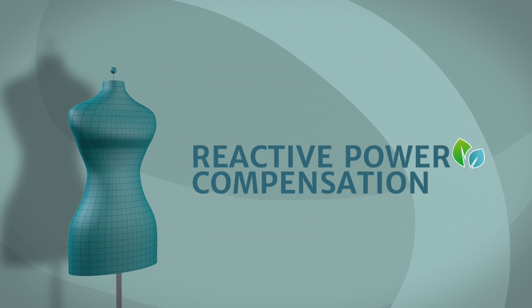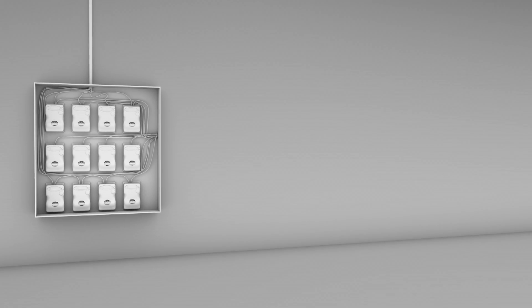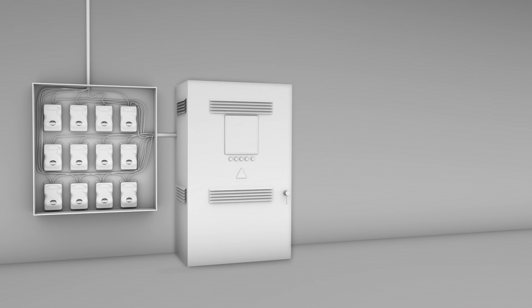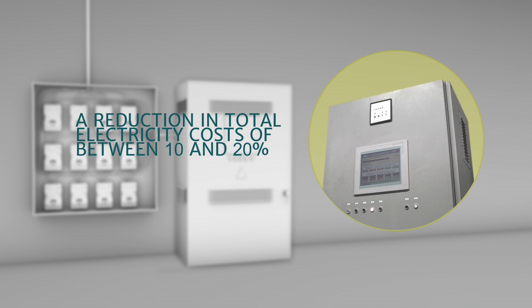The reactive power used by electric motors is stored for a few fractions of a second before being released into the grid. The installation of a simple phase advancer helps reduce total electricity costs by between 10 and 20%. As soon as possible, we installed power correction units in order to compensate for reactive consumption. The total reduction achieved was 20% compared to the previous invoice.